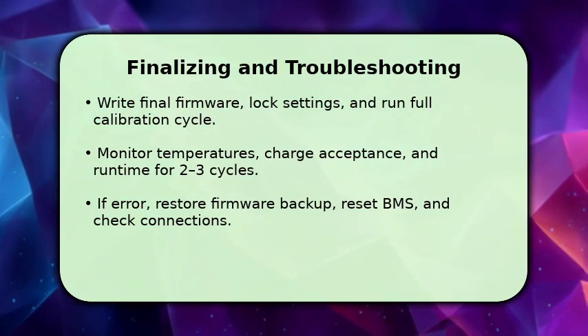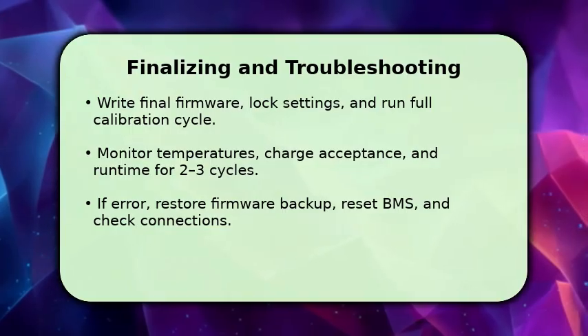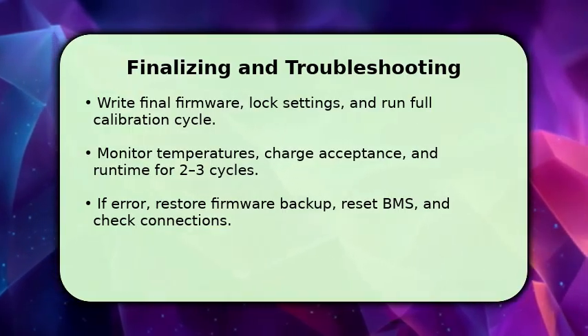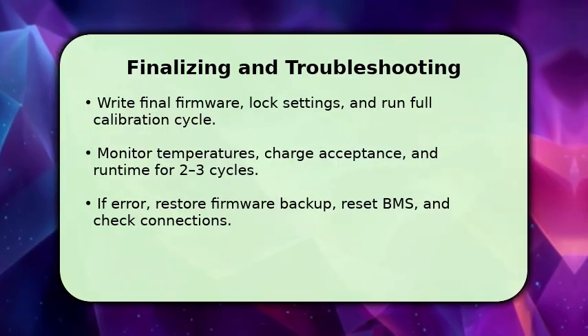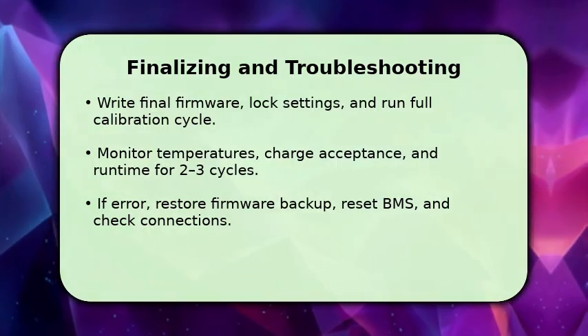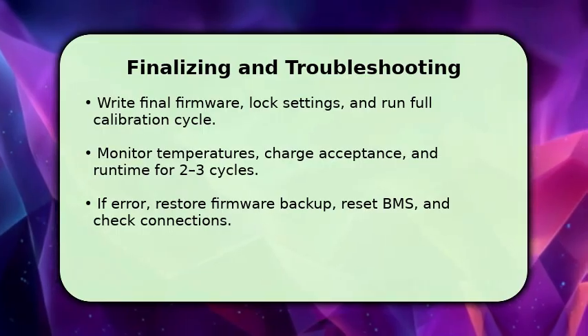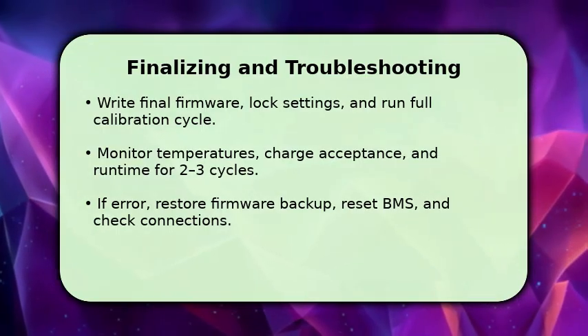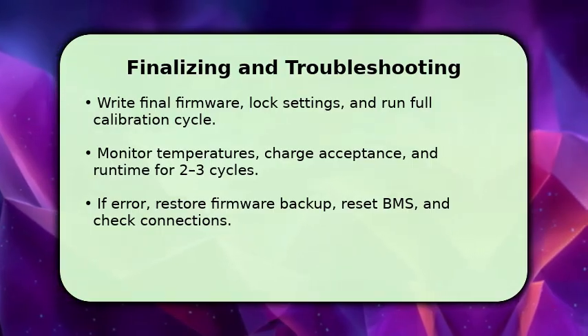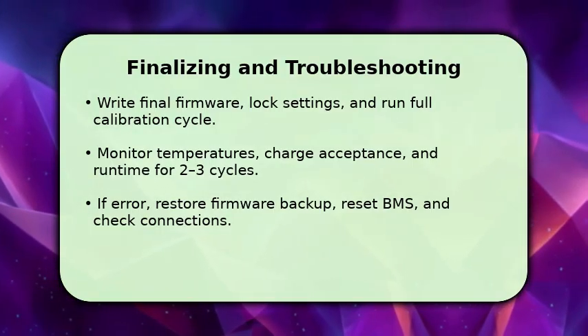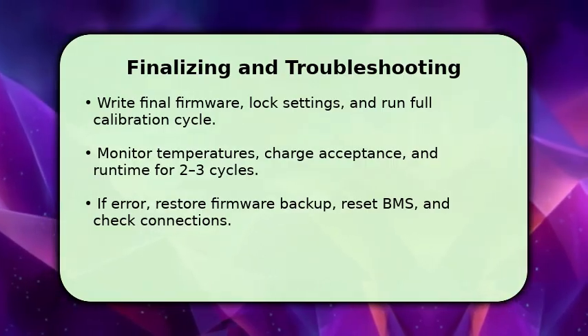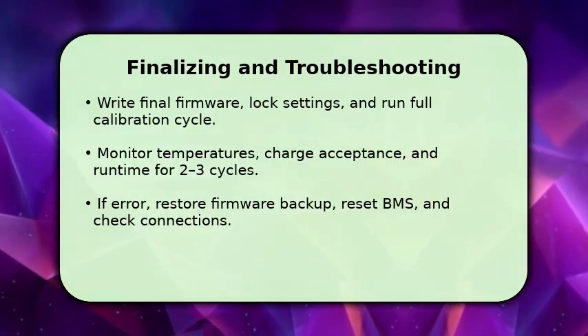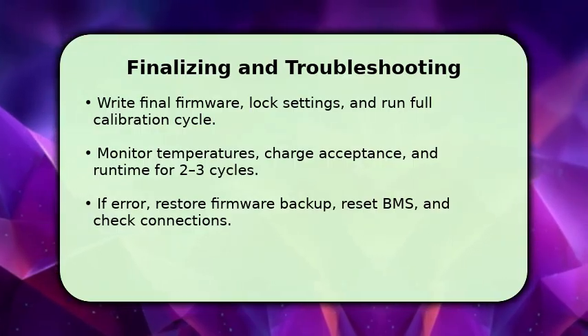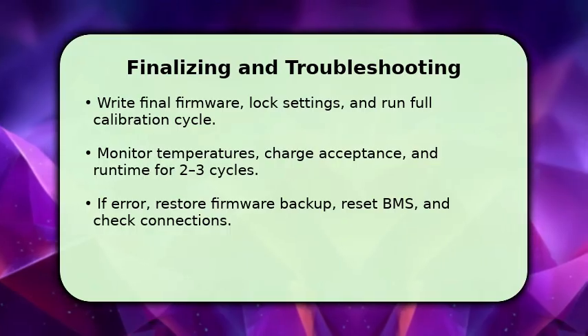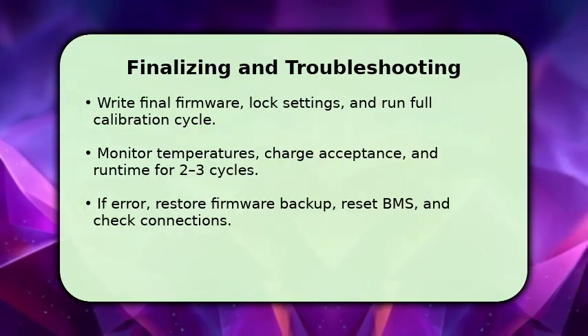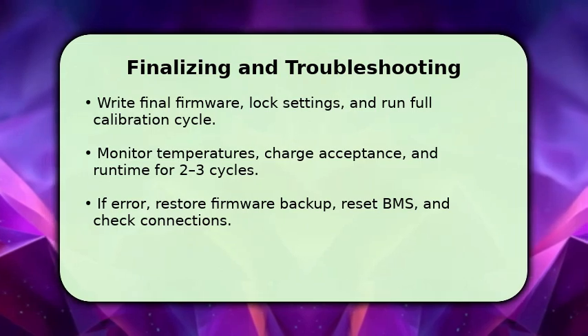You finalize by writing the verified firmware and locking configuration bits so settings persist across reboots, then perform a full calibration cycle to let the BMS relearn capacity. Make sure to monitor cell temperatures, charge acceptance, and runtime over 2 to 3 cycles to confirm improvements. If anything goes wrong, such as unexpected shutdowns or errors, restore the firmware backup, reset the BMS, and recheck all physical and communication connections. This usually resolves programming-induced faults.